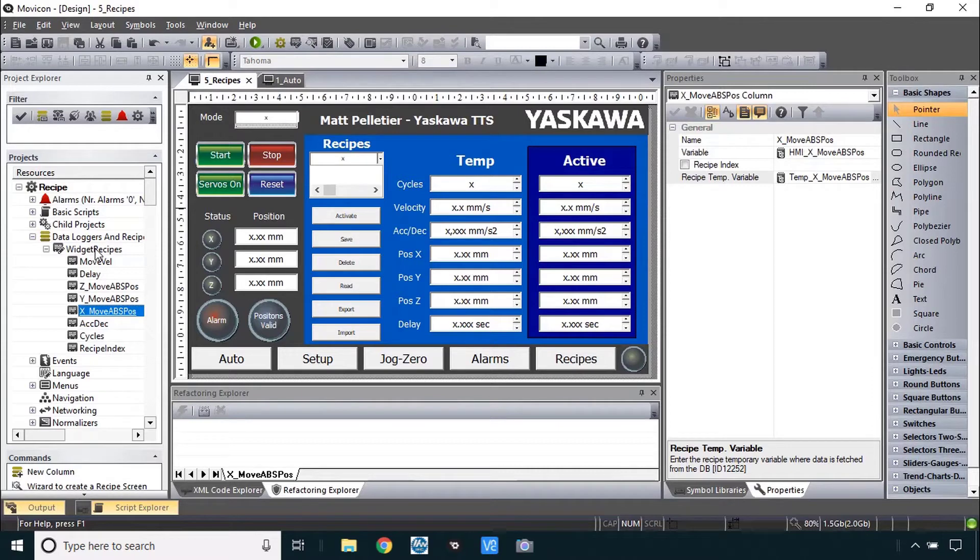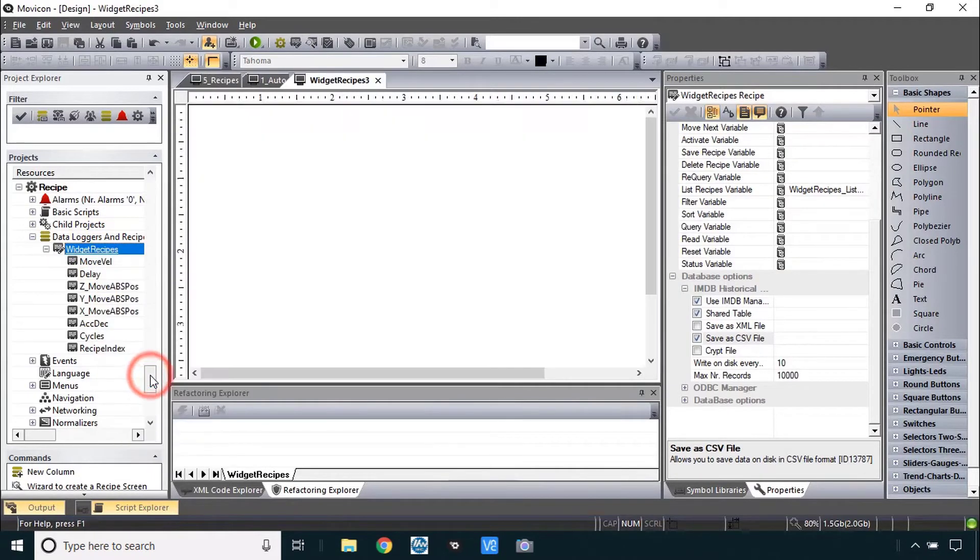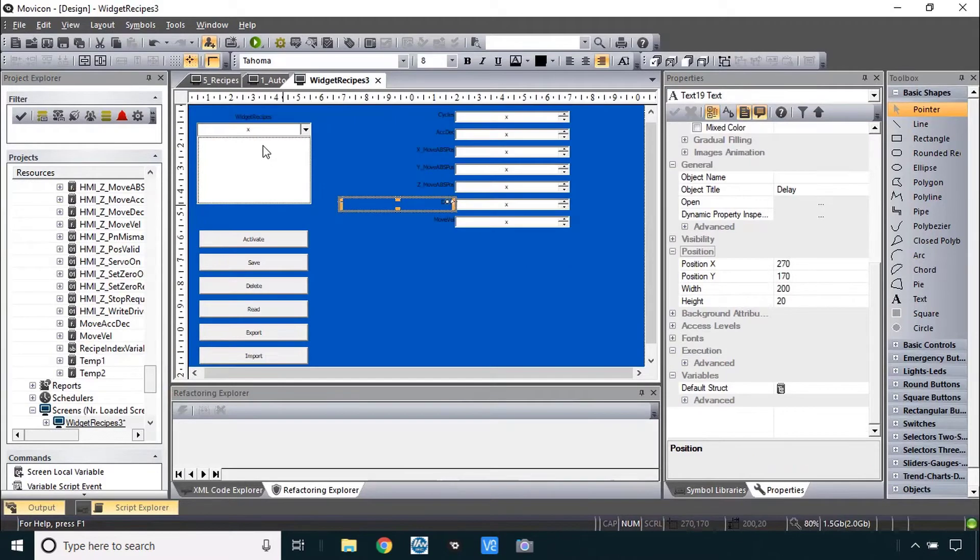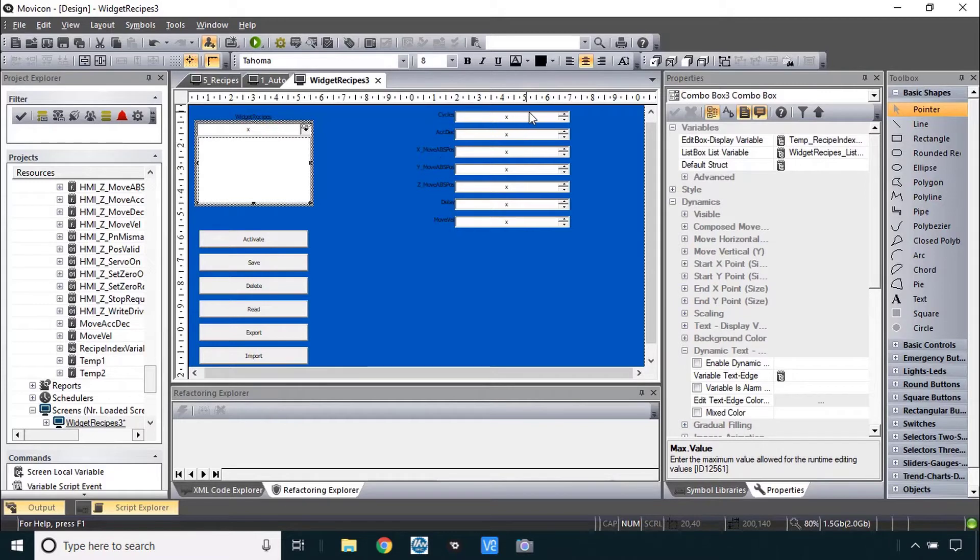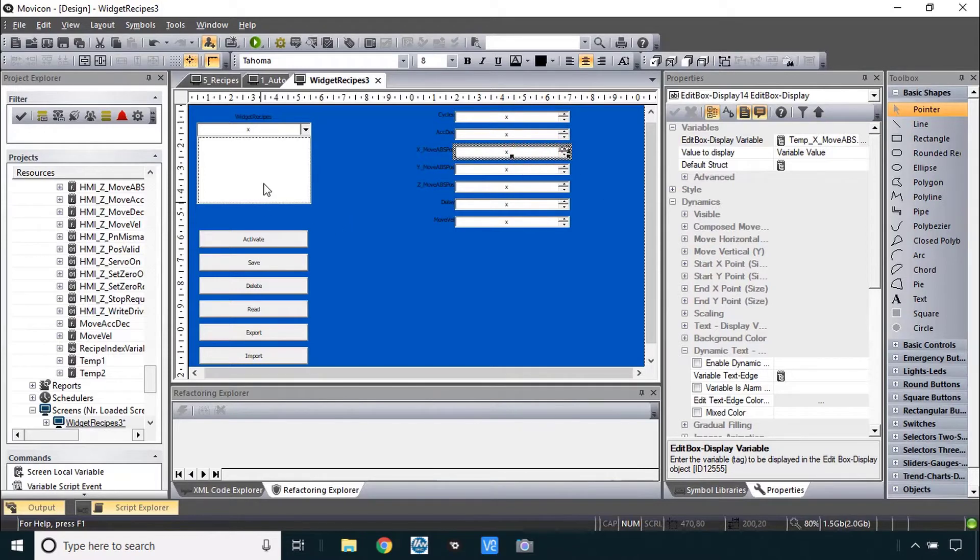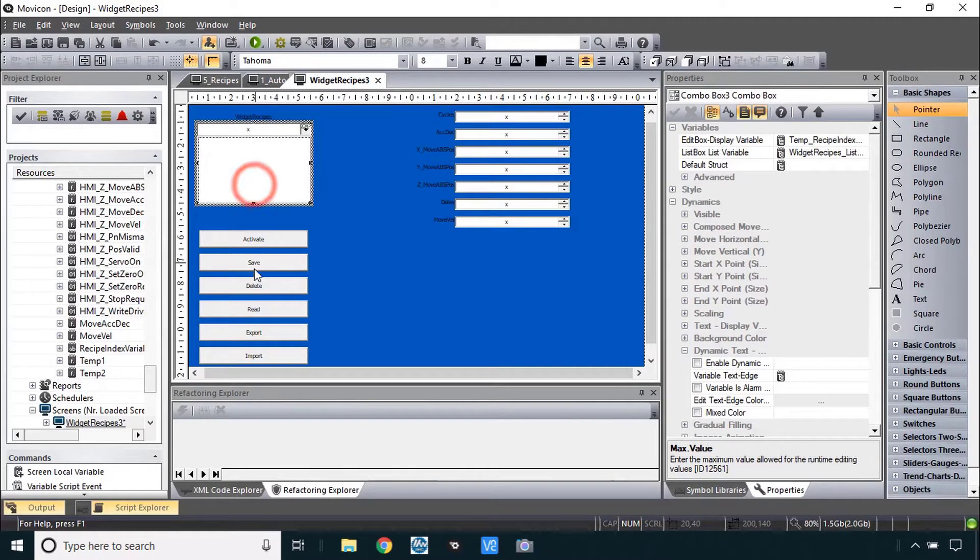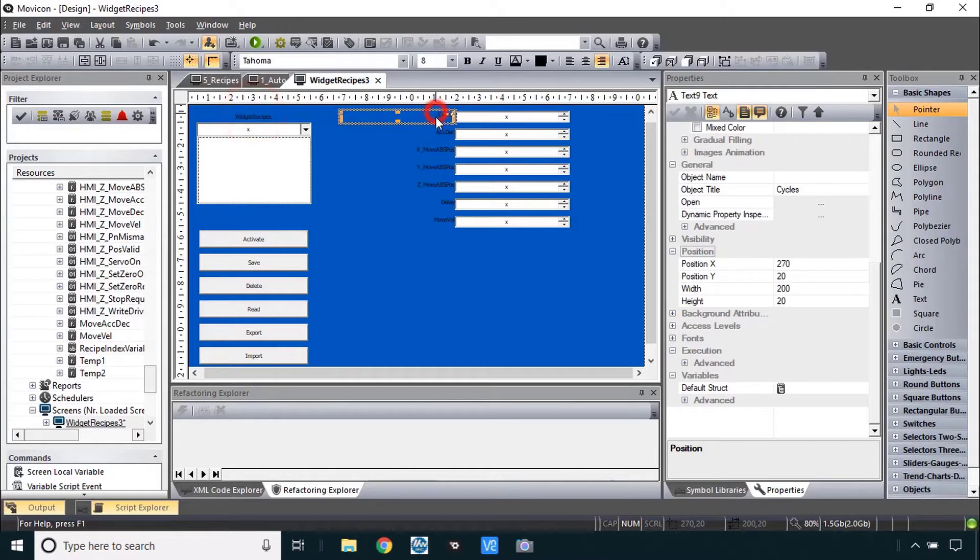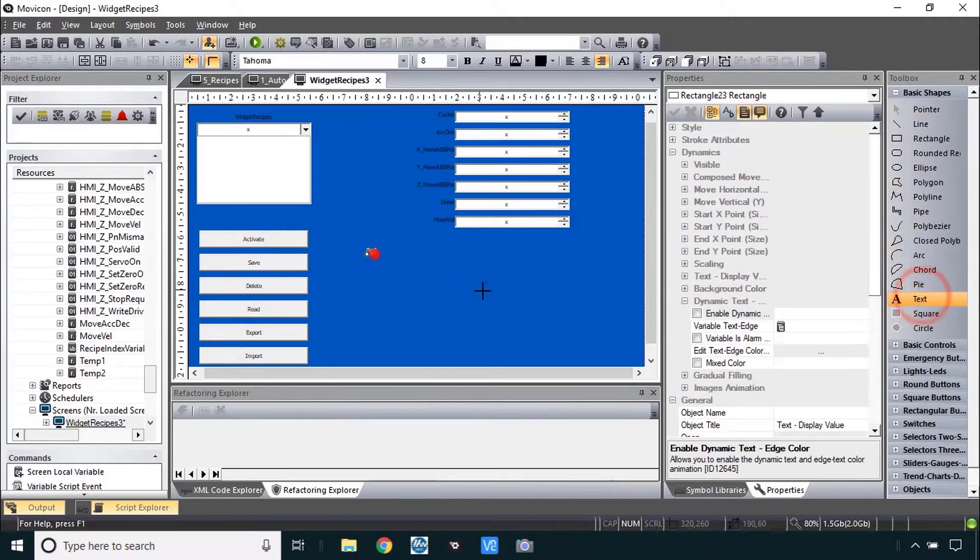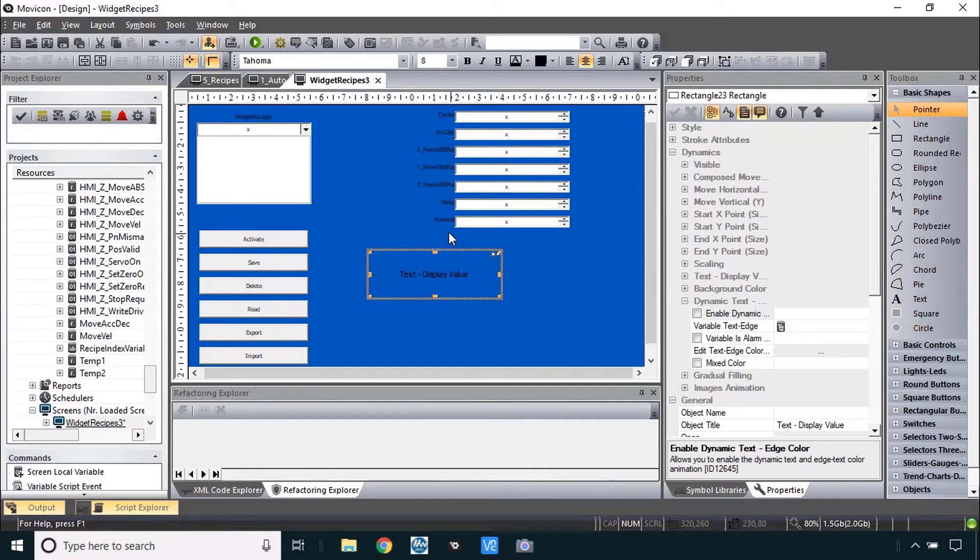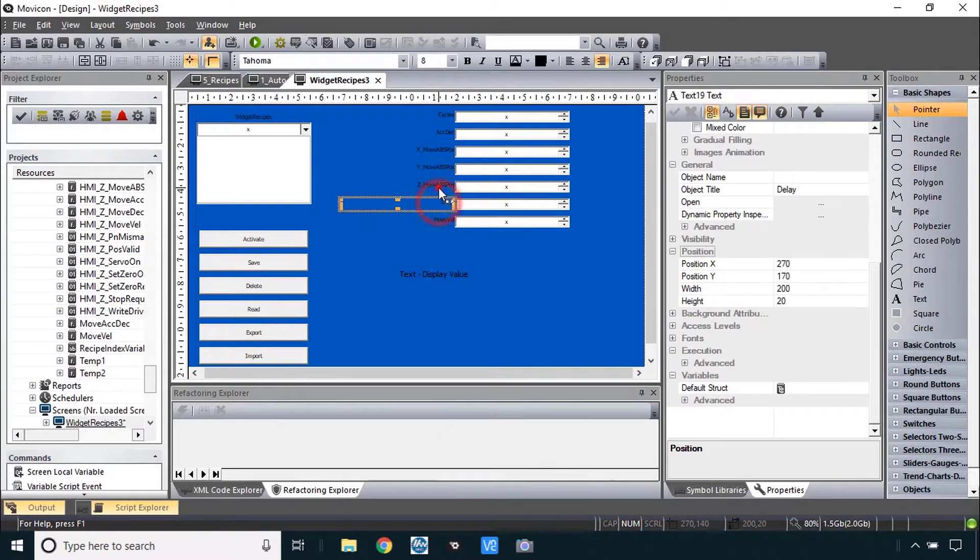The software has built in a way to right click and create the recipe screen automatically. That generates this drop down list, the buttons, and it makes some labels here and edit box displays with the correct temp variable in it. I'm going to recommend you use these items on the left but don't use the text boxes. The reason is that the formatting options are very limited. This type of text box is different than the type you've been using. It's actually a rectangle with text in it. This is a literal text box and it can only use certain system formats and colors for example.